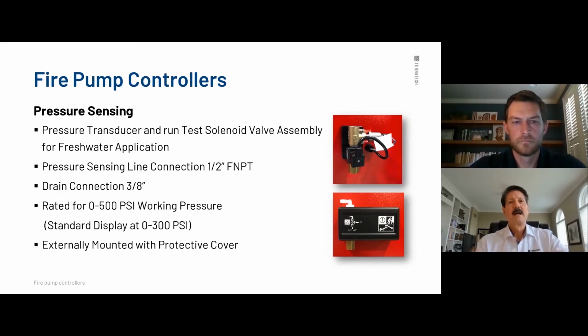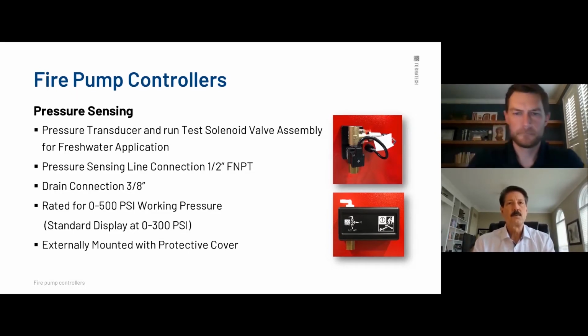Pressure sensing, obviously. How does a fire pump controller operate? Well, quite easy. We have a pressure sensing line that's roughly a ½ inch, comes into a pressure block, and really the key to this is the pressure transducer. As you can see in this picture right here, we have the pressure transducer here. We have a test solenoid up on the top part here. And without getting into too much detail there, the pressure transducer will actually activate knowing the pressure of the line itself, send a signal to the operator, which is the brain, and determine whether or not we're below cut-in or above cut-out.